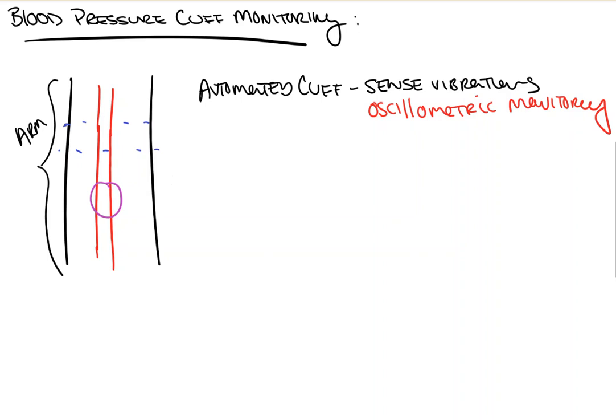There are vibrations through the air that's inflated the cuff, and they're transmitted from a physical signal to an electrical signal. And they actually measure the MAP directly, not the systolic and diastolic pressure, but they measure the MAP directly. And that's at the point of maximal vibrations. Again, point of maximal vibrations, same thing as the mean arterial pressure. The computer then, using an algorithm, goes back and calculates the systolic and diastolic pressures. So, like I said, conceptually the two work the exact same way, automated and manual, but their end measurement is different.